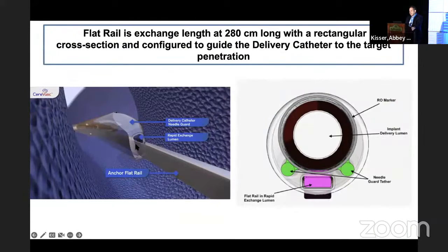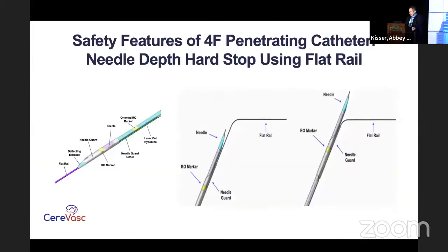So again, this is the flat rail that you see. This is the needle guard that protects it. There's 2 wires that enable us to retract the needle guard. And as you can see, the flat rail enables a much lower profile for the system. If it was a round wire, it would make the whole system larger. And so the system is about 4 French, 4.2 French in size.